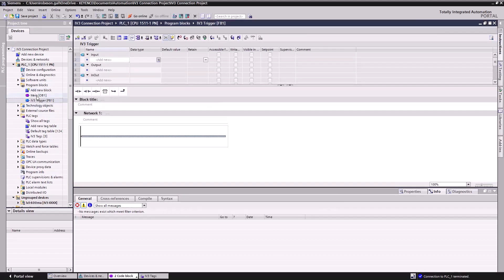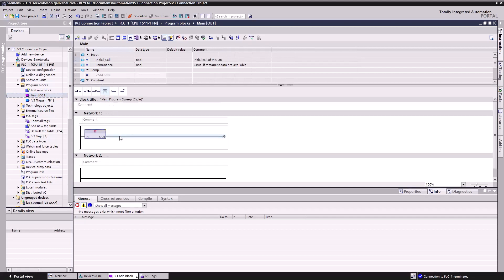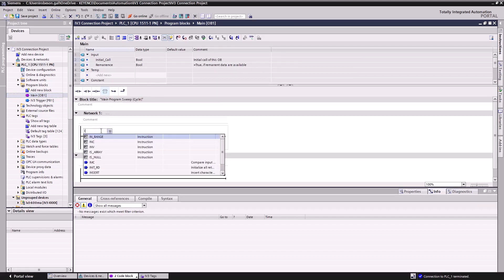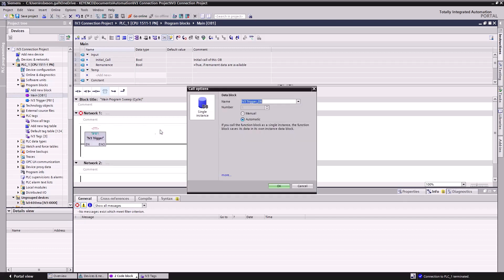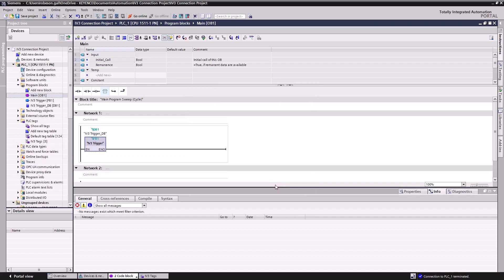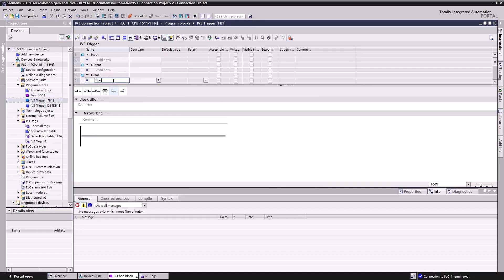Double-click Main OB1 to go to our main routine, and drag and drop the block element onto Network1. Then assign it as IV-3 Trigger. This will prompt us to create a data block, which will store the data for our function block. Click OK, then double-click the IV-3 function block. Here, we'll have to create one last tag in our data block under the In-Out section. We'll name it Start Trig.